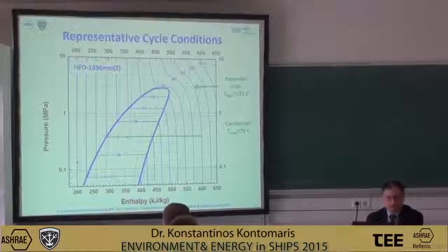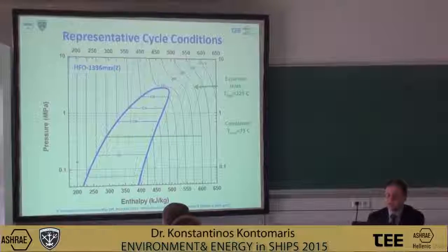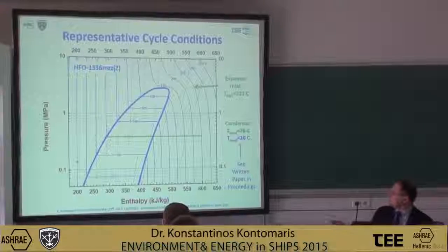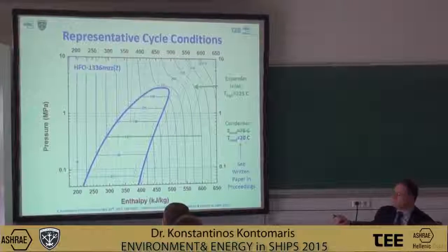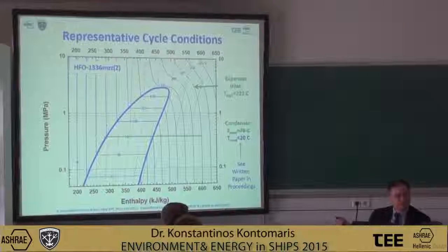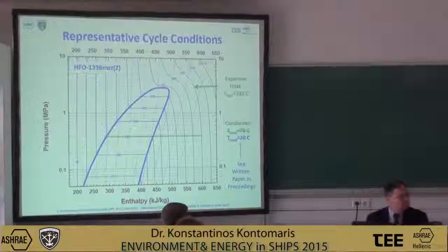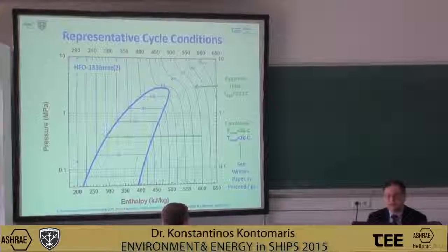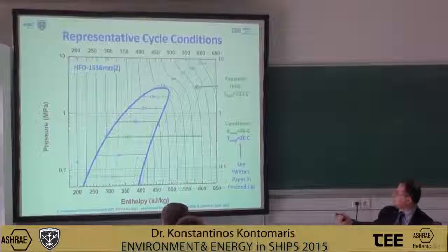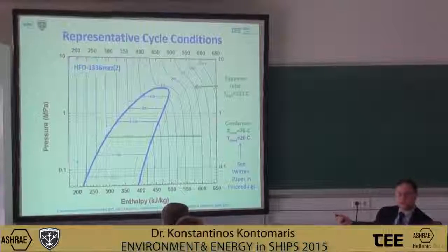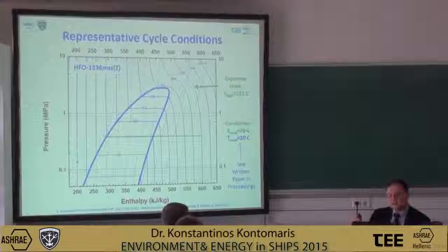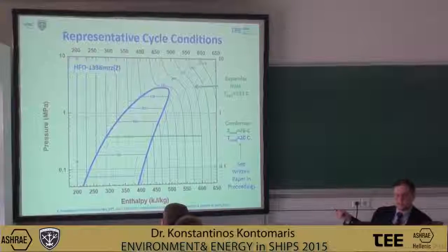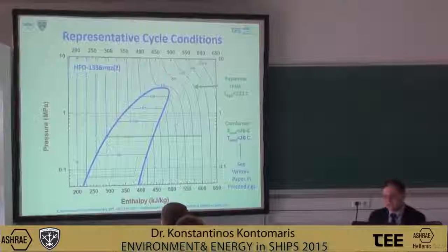If such a heating duty does not exist, then it would be advantageous to run the condenser at the lowest possible temperature, and access to seawater allows a relatively low condensing temperature of 20 degrees. The written paper to the conference presents an analysis for that case.